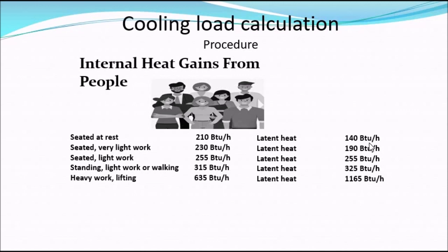Seated for very light work is 230 BTU/hr with a latent heat of 190 BTU/hr. Seated light work is 255 BTU/hr with a latent heat of 255 BTU/hr. Standing light work or walking generates 315 BTU/hr with a latent heat of 325 BTU/hr. Heavy work or lifting generates 635 BTU/hr total with a latent heat of 1165 BTU/hr.